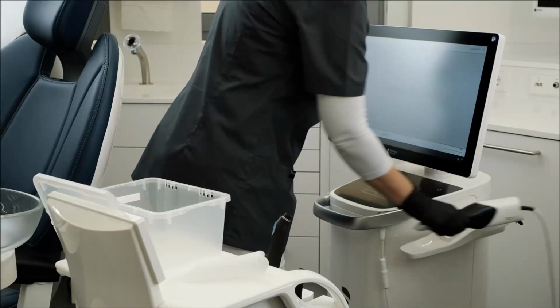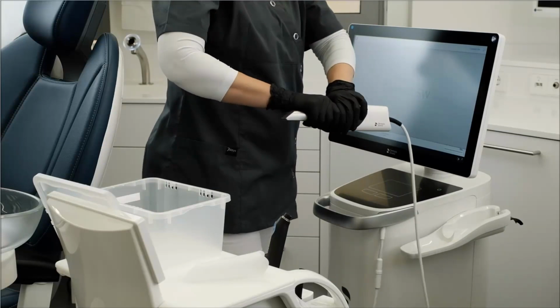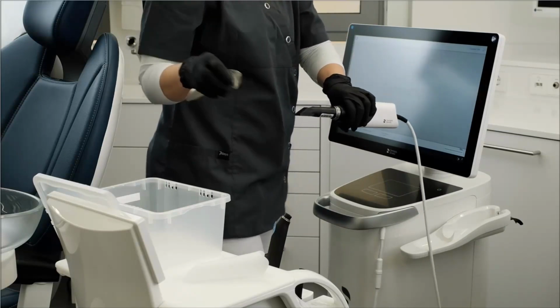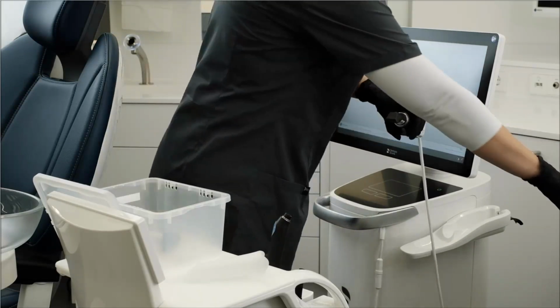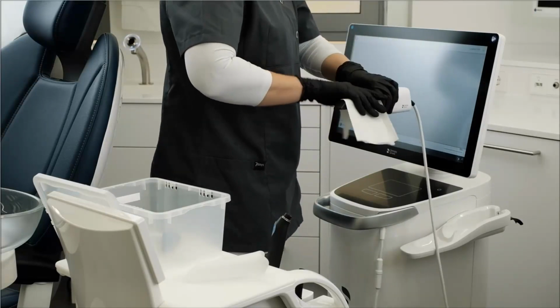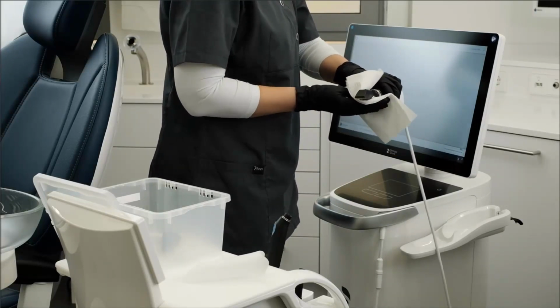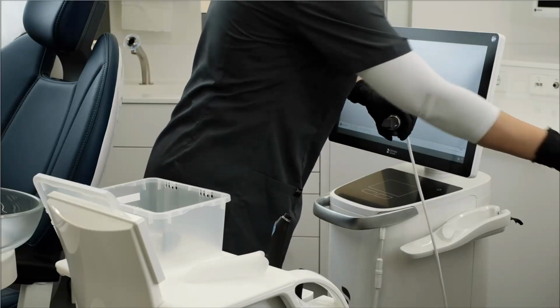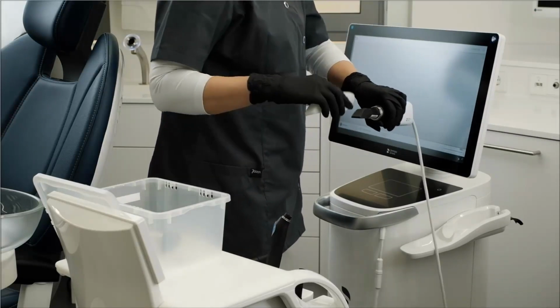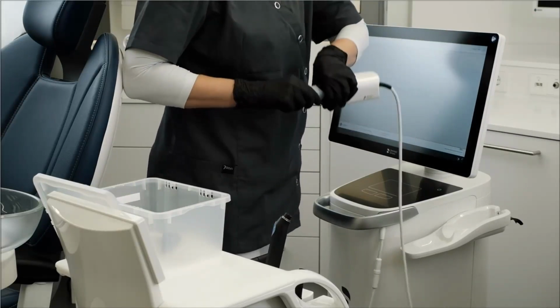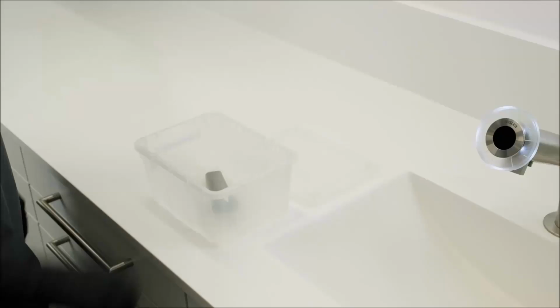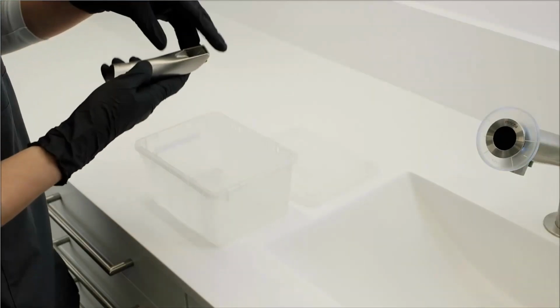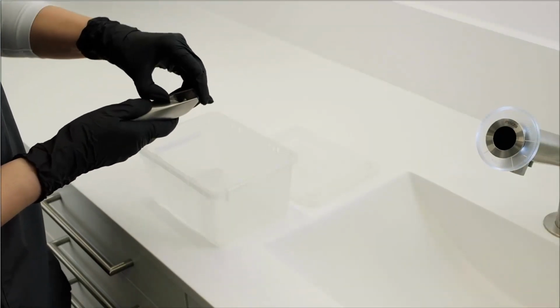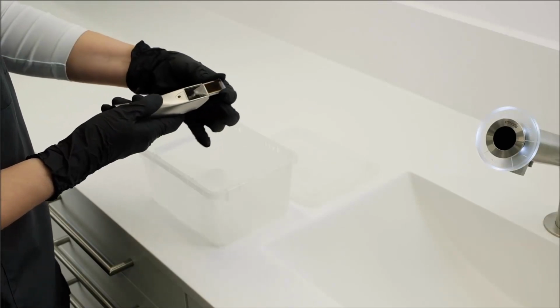Now remove the autoclavable sleeve from the scanner, wipe the tube with a lint-free dry cloth, and reattach the white protective sleeve. Before you start the processing, remove the disposable window. Lift the window at the notch and slide it out through the guide tracks.